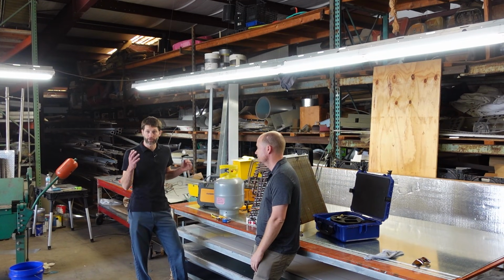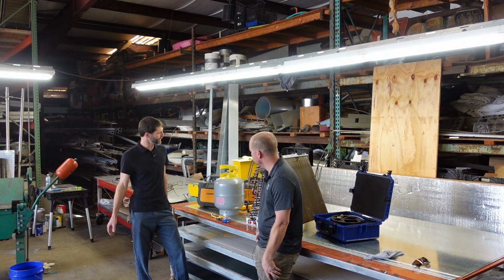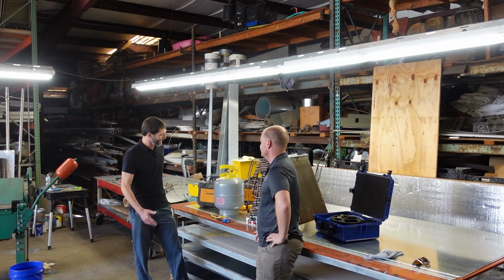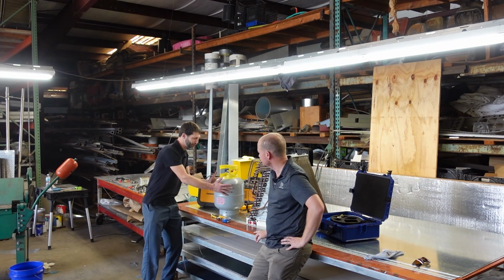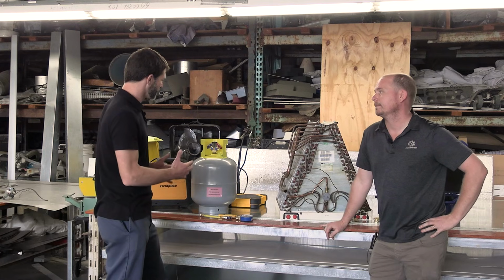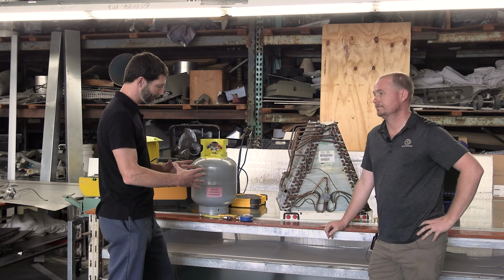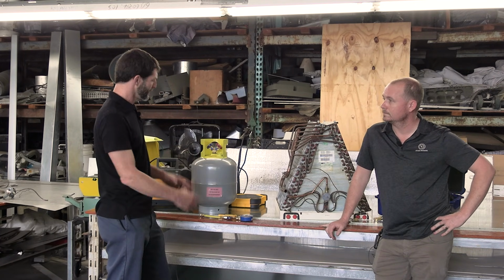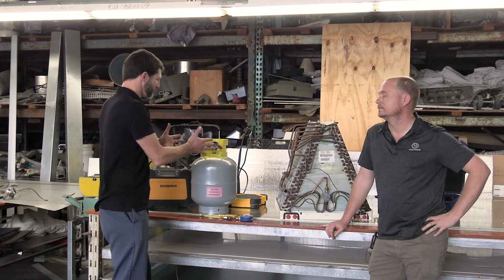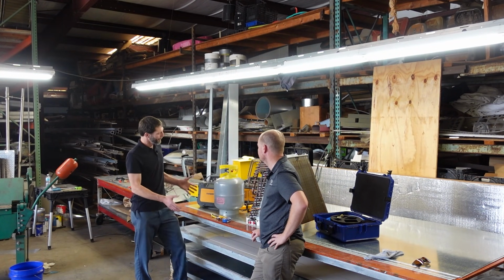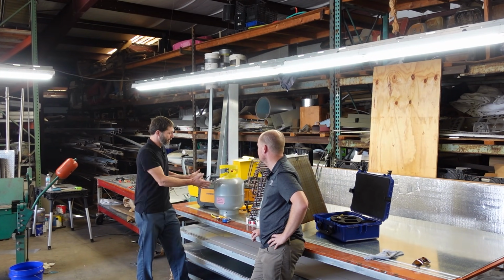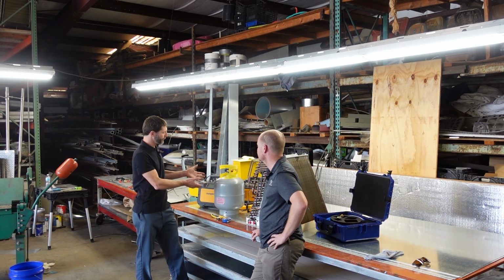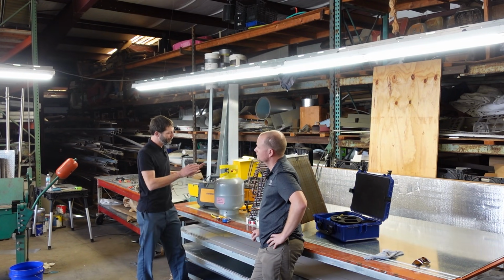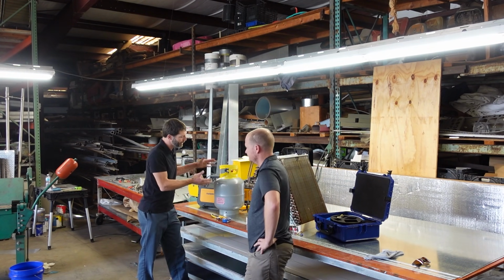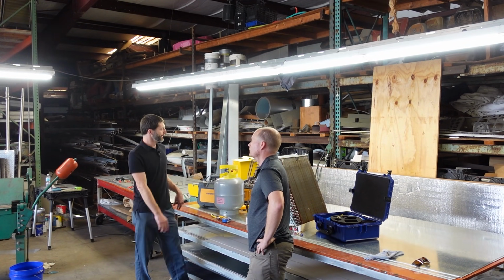Yeah, so you're going to have several recovery tanks in the truck, and each one's going to be a different refrigerant. And I know it's harder to keep 50-pound recovery tanks in the truck, but if you're just going around with the 30-pounders, the smaller versions, even, they're not exactly 30, and these aren't exactly 50. They're less, but they don't have a lot of capacity in them, and you're going to overfill, or you're going to have to change out. You don't want to overfill them, and you don't want to have to stop your recovery process and switch out the tank for another one.